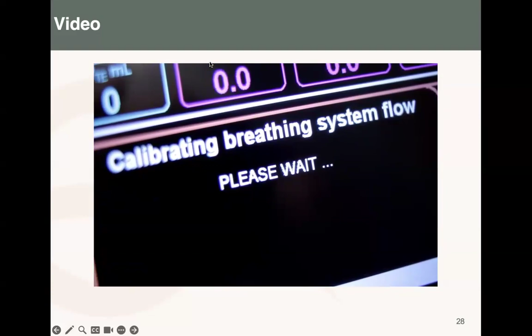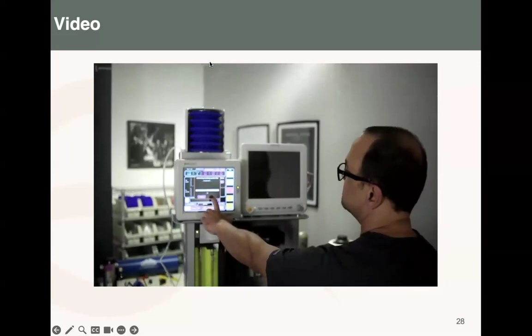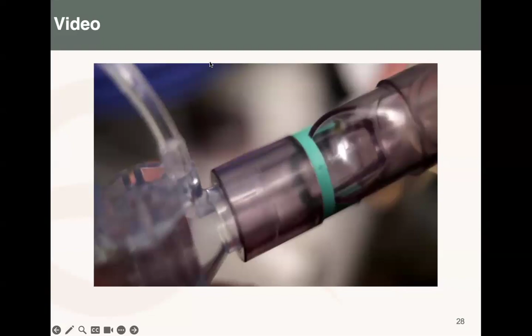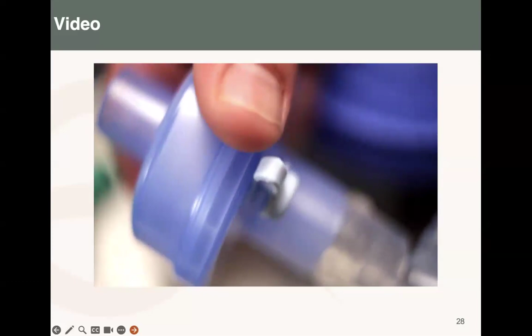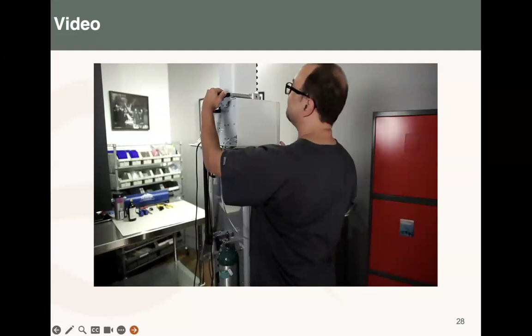If it fails again, you must perform a pressure transducer zero offset calibration, followed by the flow sensor calibration. If it fails again, replace the flow sensor with a new one. If a new sensor fails the calibration, please contact Gradian for service. After calibration, reconnect the flow sensor to the patient circuit Y piece and place a clean patient bacteria filter ready for the next case. Reconnect the ventilator drive hose between the bellows 17mm taper and the UAM anesthesia machine ventilator connector.